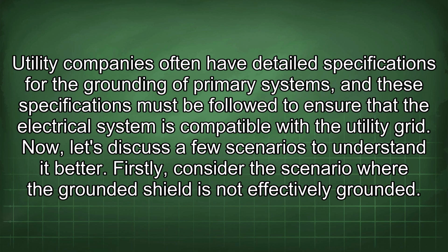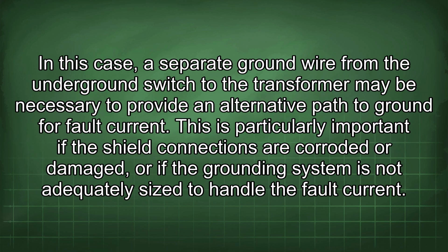Firstly, consider the scenario where the grounded shield is not effectively grounded. In this case, a separate ground wire from the underground switch to the transformer may be necessary to provide an alternative path to ground for fault current. This is particularly important if the shield connections are corroded or damaged, or if the grounding system is not adequately sized to handle the fault current.